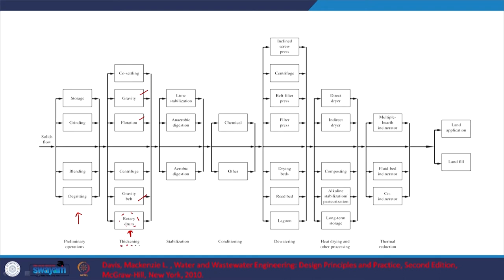After thickening we have greater solids concentration. Depending upon the type of solids, stabilization can be anaerobic or aerobic digestion. Lime stabilization with respect to pH is also required — we will look at that later. Then conditioning, typically adding chemicals so that dewaterability is relatively better. For dewatering we see different kinds of equipment: belt filter press, which is sometimes used during thickening itself, inclined screw press, and filter press. Some thermal process may be required and then land application. This is the whole cycle.